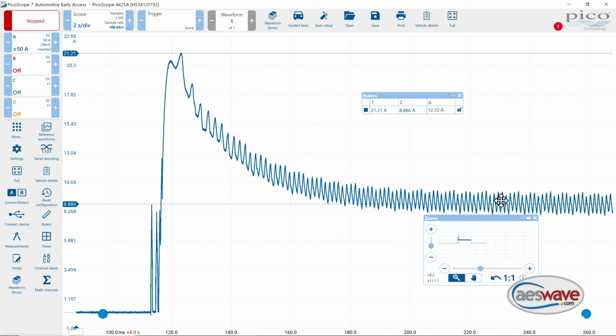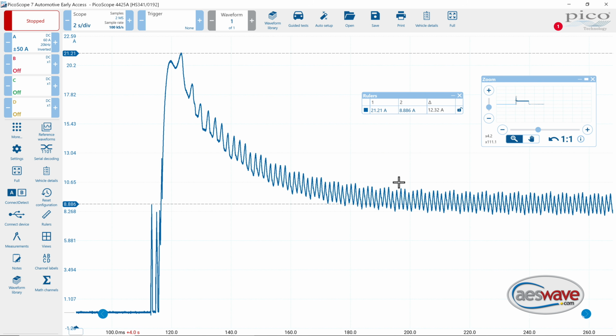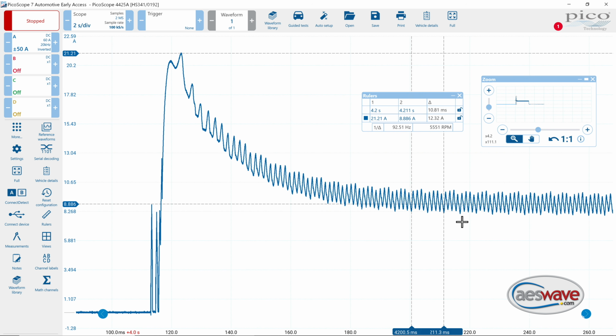And if we come over here, we want to see how fast this pump is turning. We're going to pick up two repeating pulses here to estimate pump speed, and I'm going to select that low one there. So let's count: 1, 2, 3, 4, 5, 6, 7, 8. Yep, so typically you have 8 commutator bars on your armature.